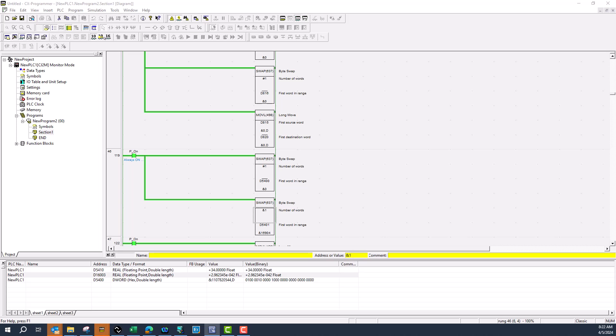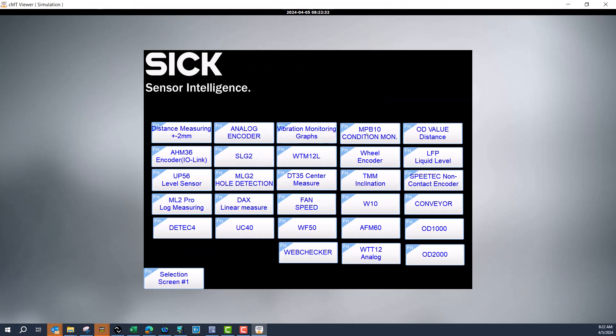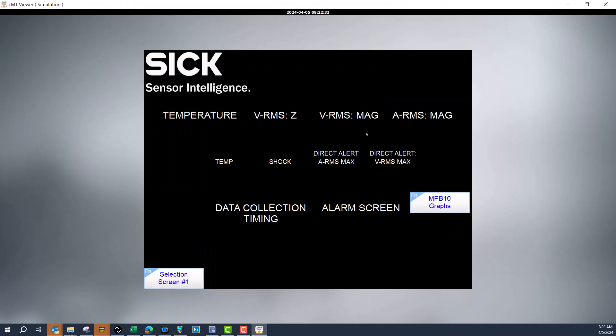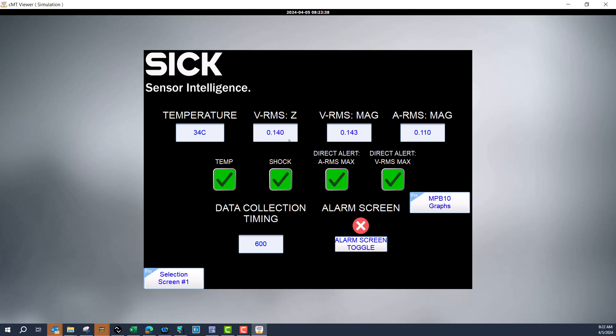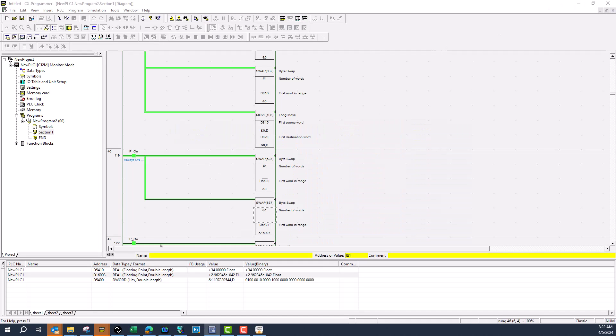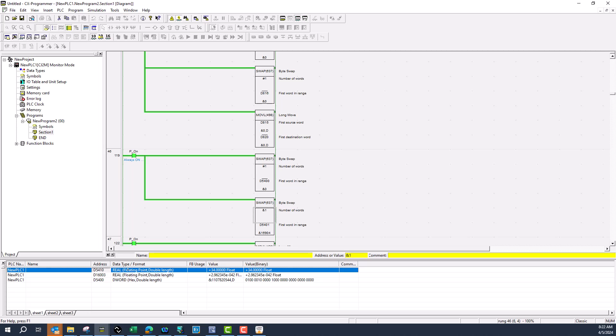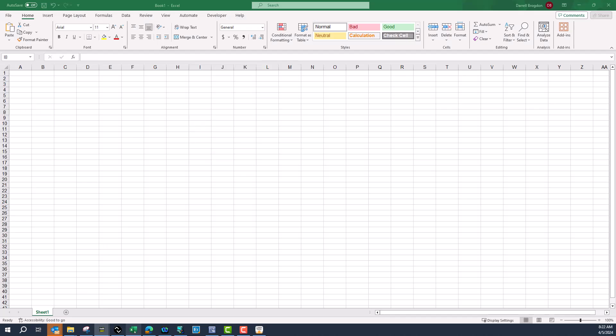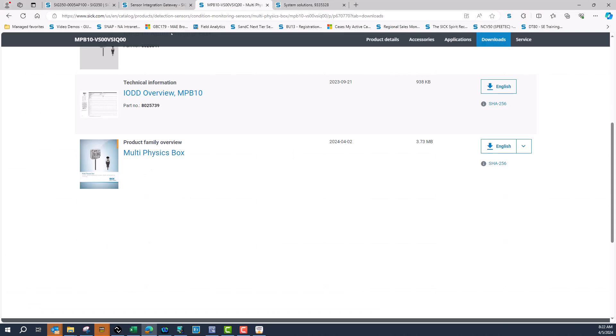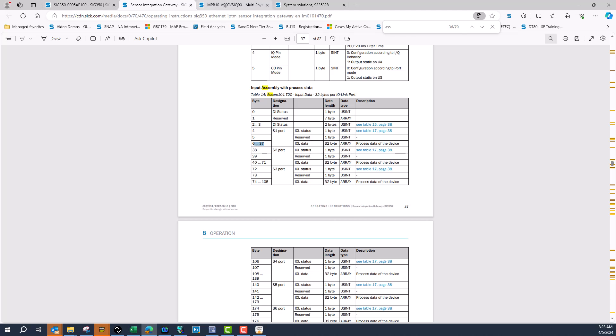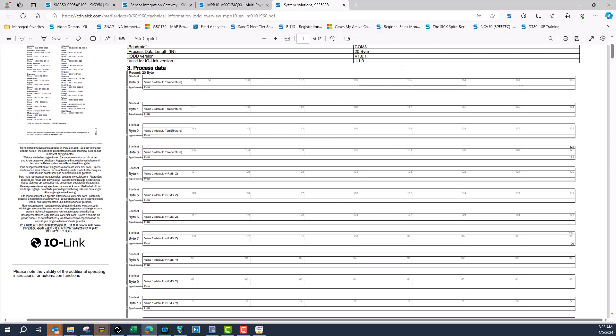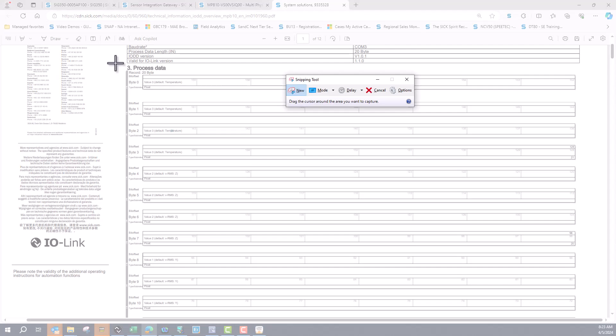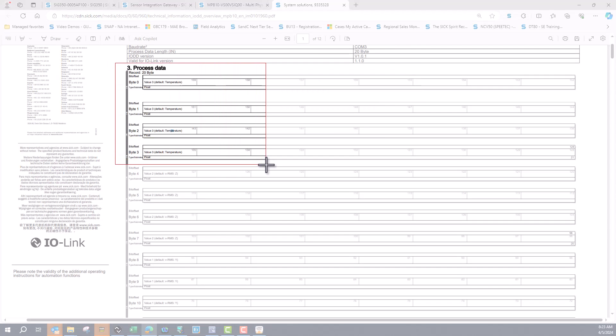I'll start the HMI back up since I timed out. Again, we see 34 degrees Celsius is the same thing that we see here in the PLC, but I'm coming in with the first byte starting at 16003. So what we have to do is a word swap and a byte swap. I'll go ahead and make a graph to make this easier to understand, and we're just going to focus on the temperature, just those four bytes.